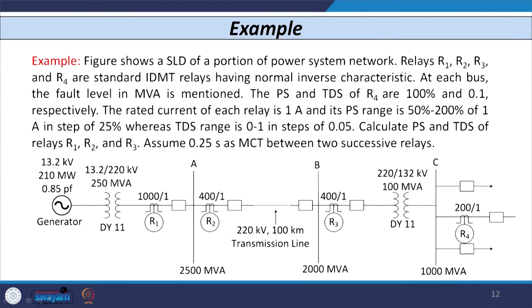In this example, the single line diagram of the network is given. There are 4 relays: R1, R2, R3, R4, and all are IDMT overcurrent relays having normal inverse characteristic. At each bus — bus A, bus B, and bus C — the fault level in MVA is mentioned, so you can calculate the magnitude of fault current using the given voltage level. The rated current of all relays is 1 ampere. The plug setting range is from 50 to 200 percent of rated current in steps of 25 percent, and the time dial setting range is 0 to 1 second in steps of 0.05 second.